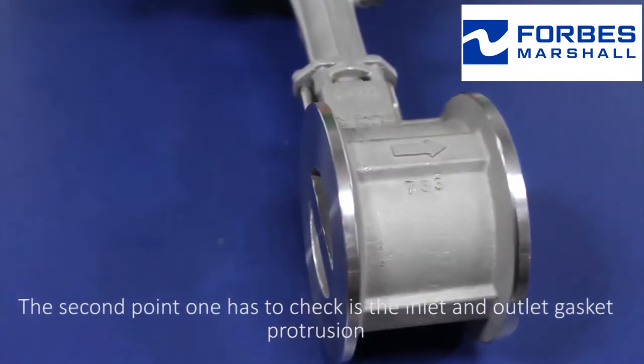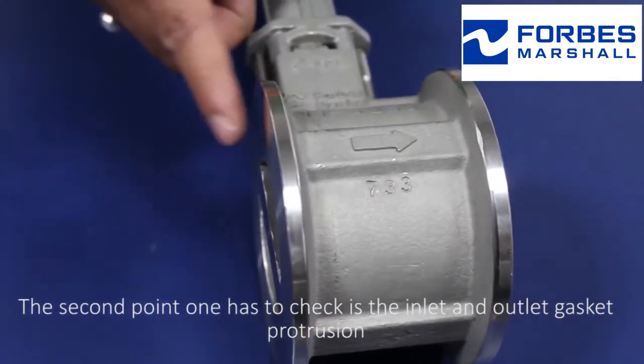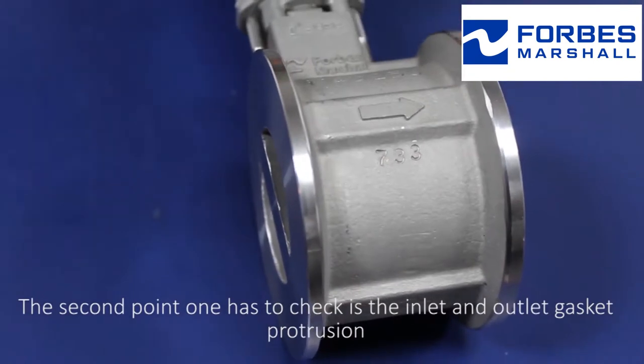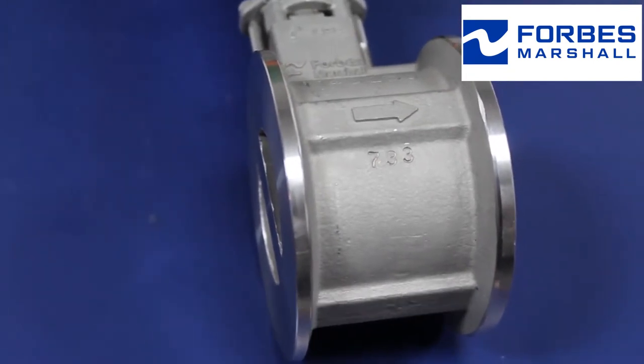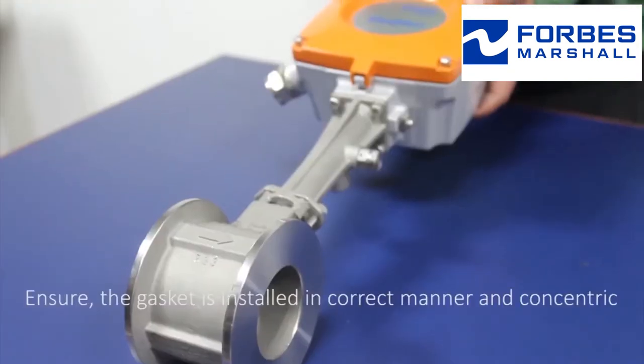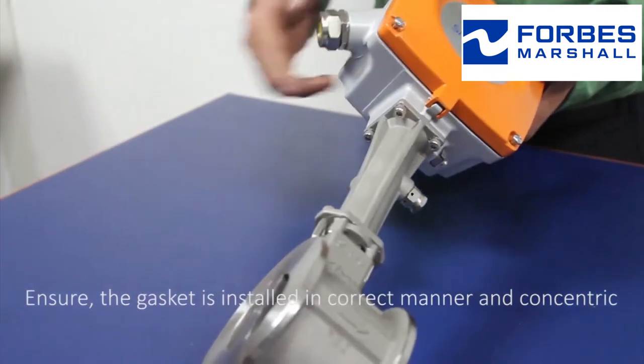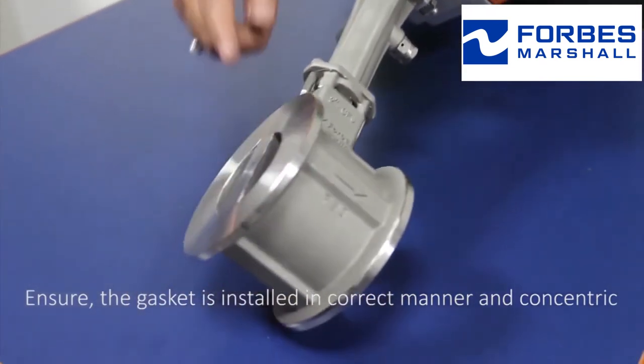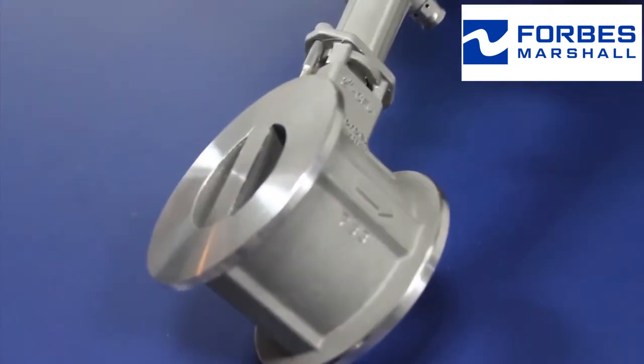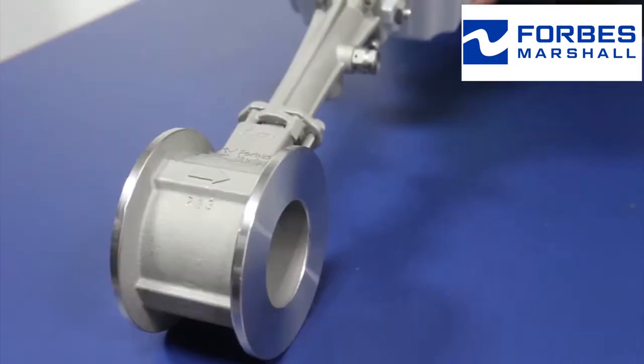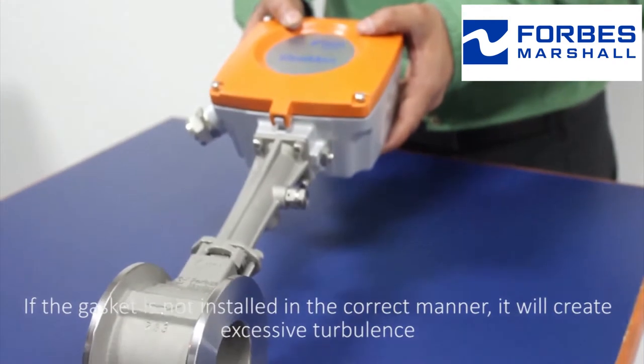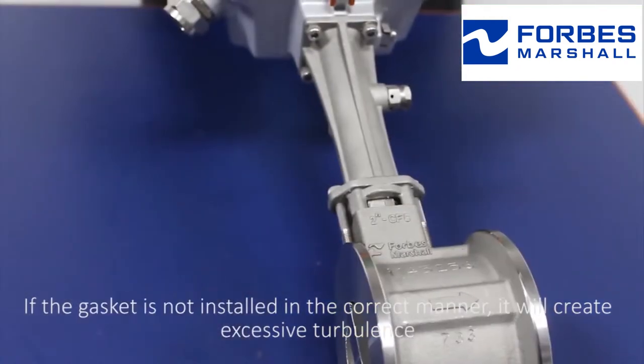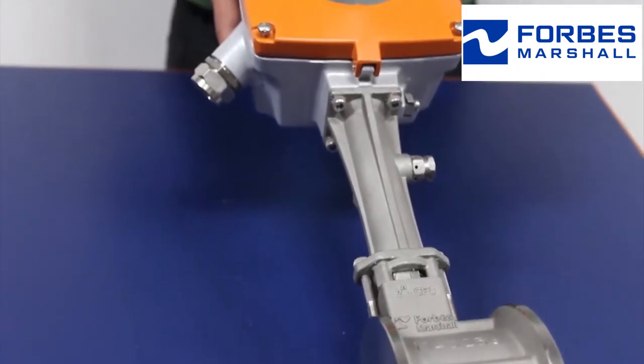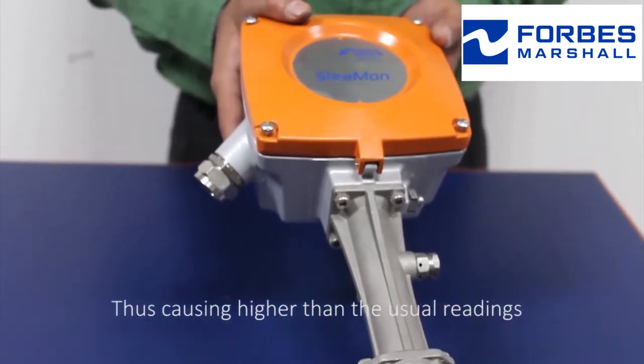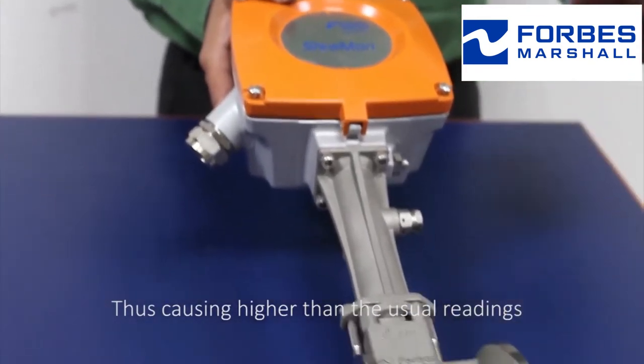The second point one has to check is the inlet and outlet gasket protrusion. Ensure that the gasket is installed in the correct manner and concentric. If the gasket is not installed in the correct manner, it will create excessive turbulence. This causes higher than usual readings.